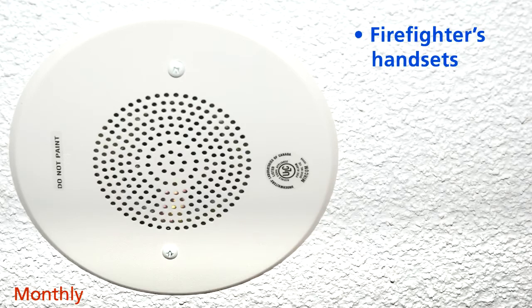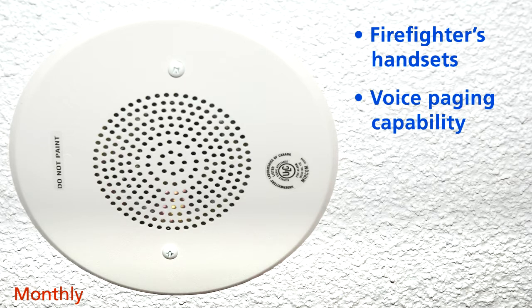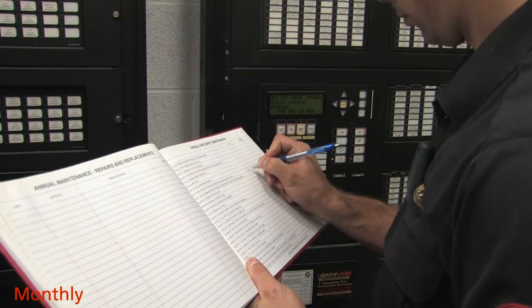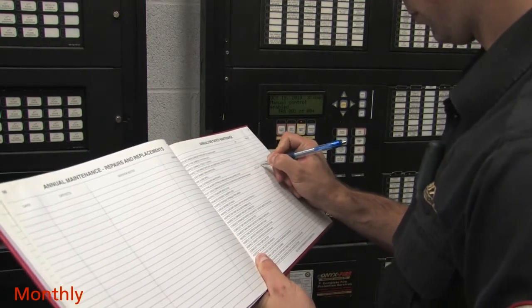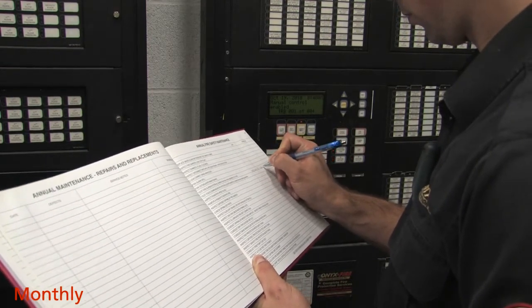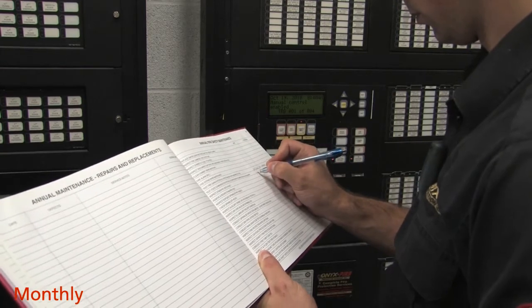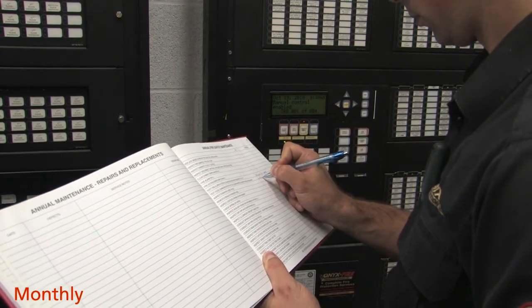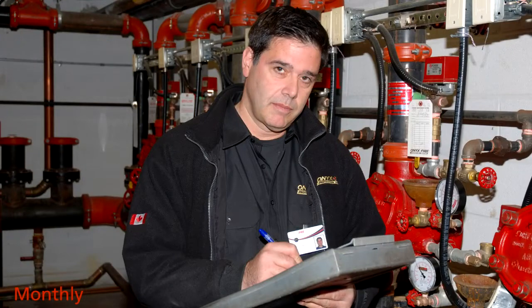Firefighter's handset for clear two-way communication with the control panel. Voice paging capability and loudspeakers operated as an on-call signal. It is important that these monthly tests be recorded in the building's fire log book. While the tests can be carried out by properly trained site staff, it is recommended that they be done by a qualified fire protection contractor.